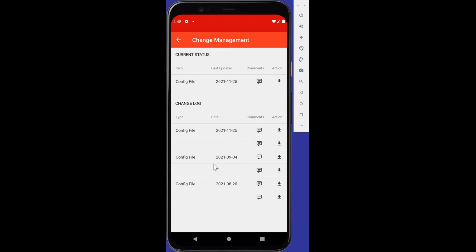And so in the past, that might mean that until the next time an Armstrong certified service provider shows up, that pump may not be running optimally. Now with the mobile app, standing in front of that pump, if you have Pump Manager, we can see what the latest configuration file is. The pumps send the config files to our cloud. Today, I think it's weekly, but we're changing that to change of value. So when somebody changes it, and we have all the historical configuration files. So for this simulated pump, we have configuration files going back to August of 2021. It looks like there was a change made in September, another change made in November, and that's the latest configuration file. So say if we want to go back to the last time an Armstrong service tech showed up, we can go ahead and download. I'm not going to hit it now, since it's an emulated mobile app anyways.